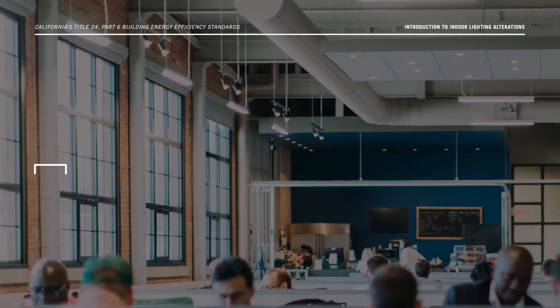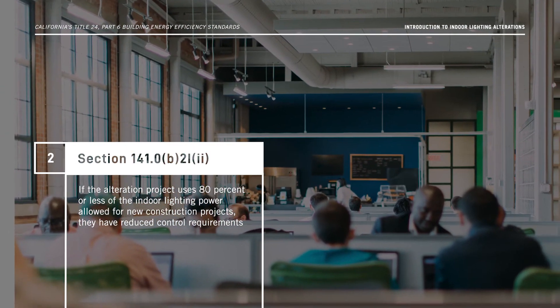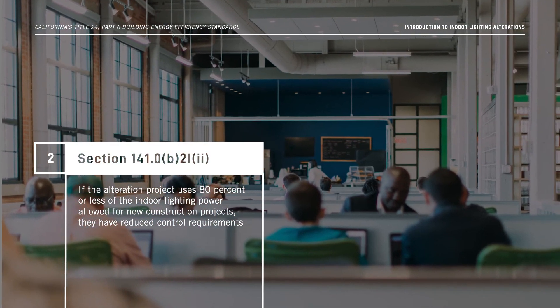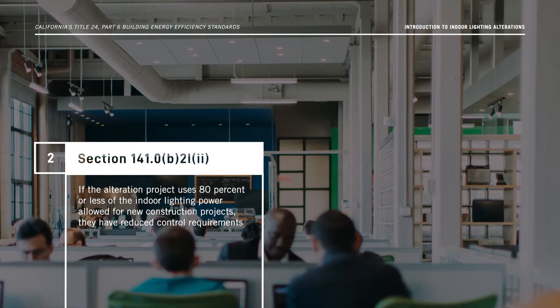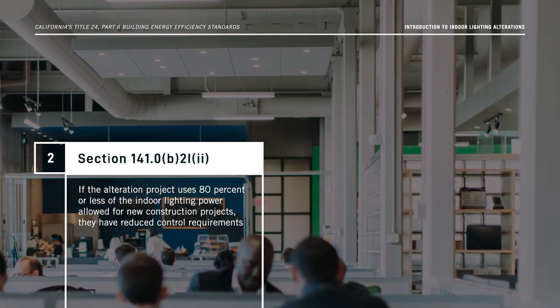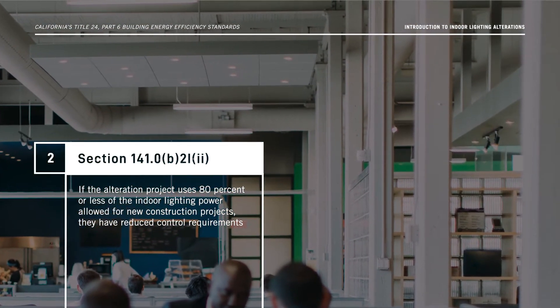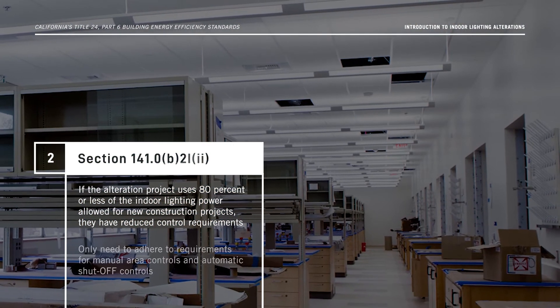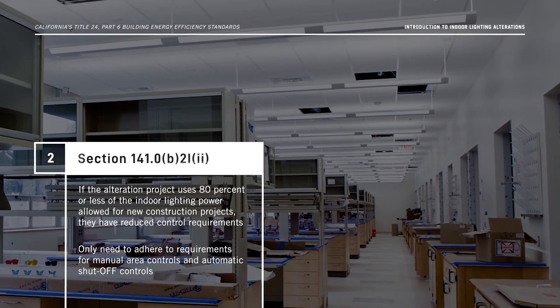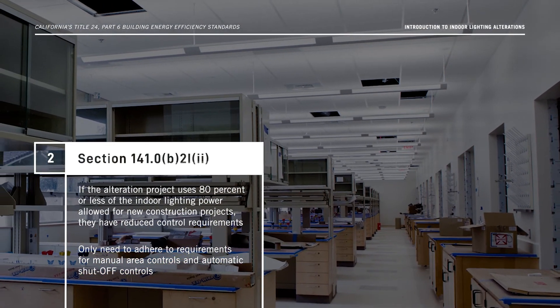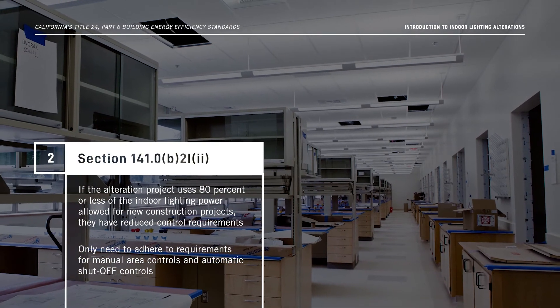Option 2: If the alteration project uses 80% or less of the indoor lighting power allowed for new construction projects, they have reduced control requirements. Projects need only to adhere to requirements for manual area controls and automatic shut-off controls.